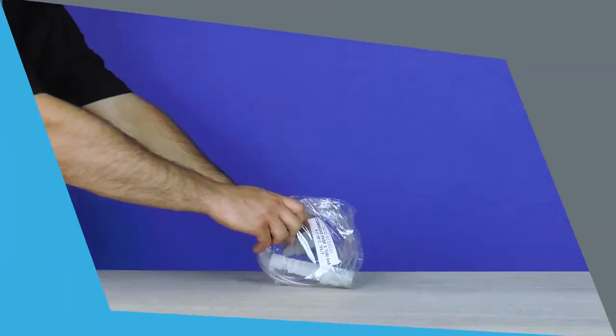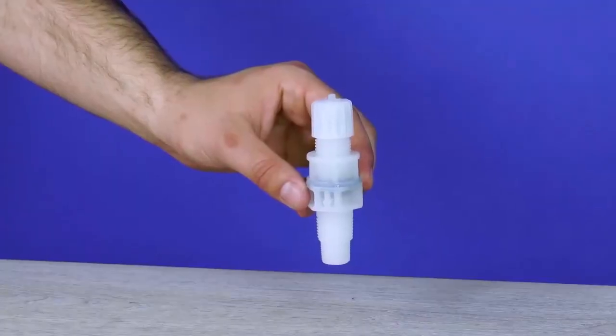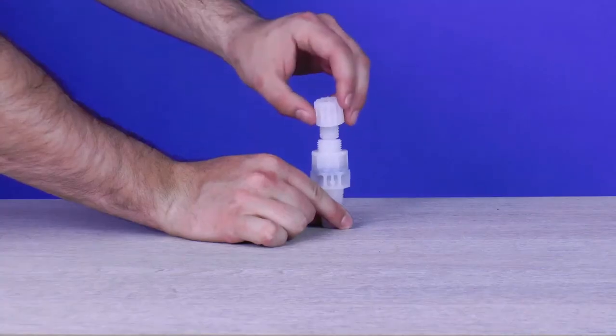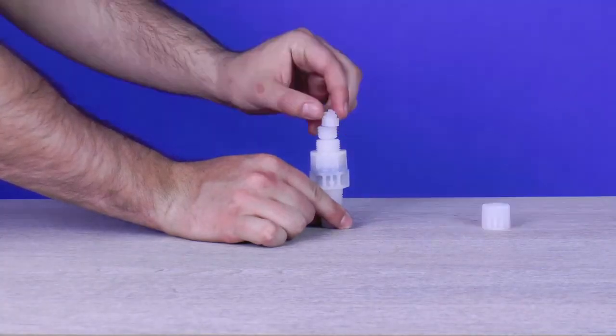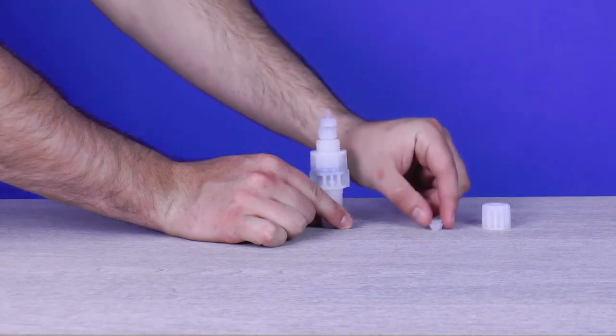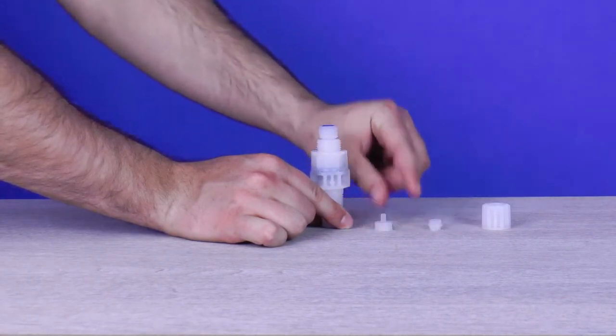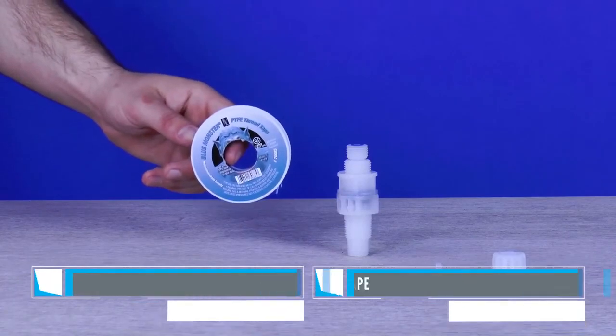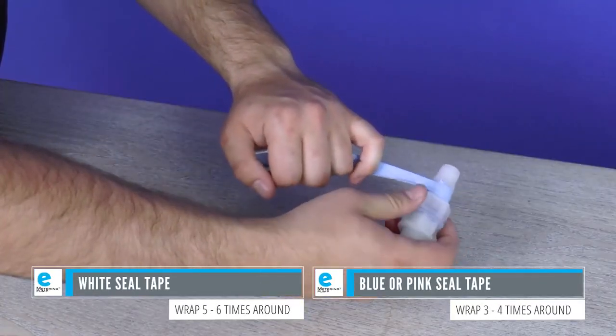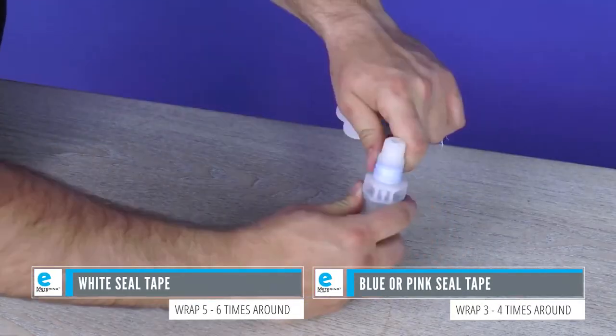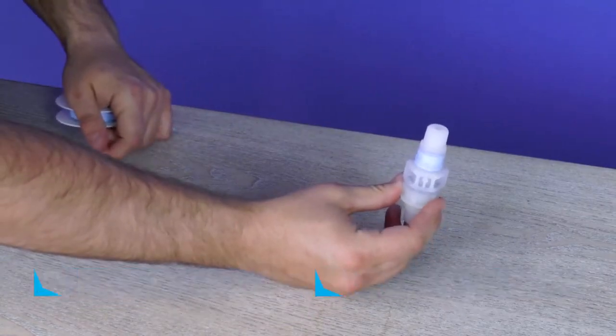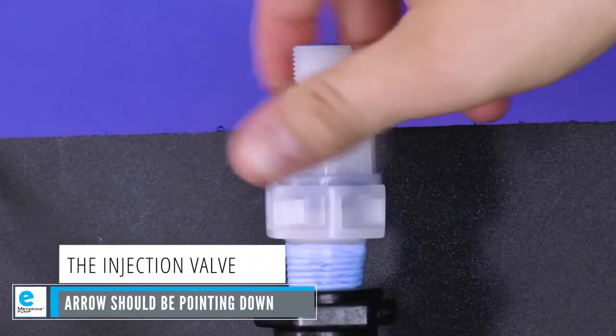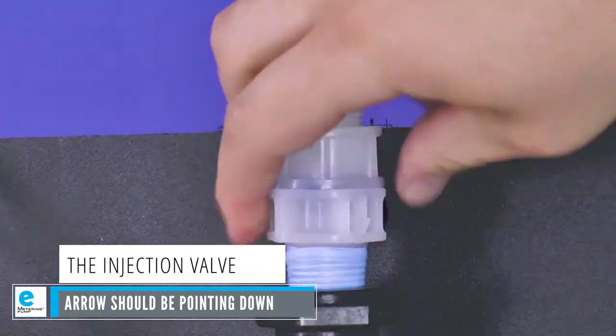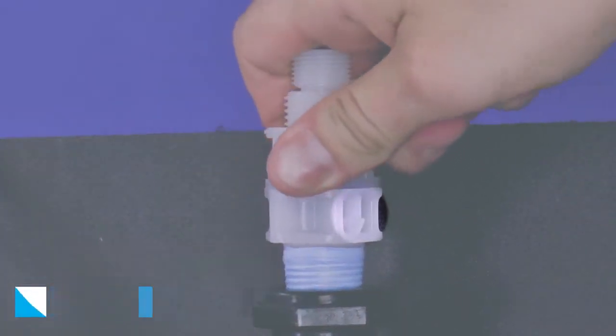Injection valve. Install the injection valve by grabbing it out of the tubing kit and remove its tube nut, collar, and nozzle. Set the connections aside. Take the thread seal tape and wrap it around the threads of the injection valve for the necessary size, either 3/8 or 1/2. Install and hand tighten the injection valve into the installation saddle or T in the supply line. Once again, do not over-tighten.